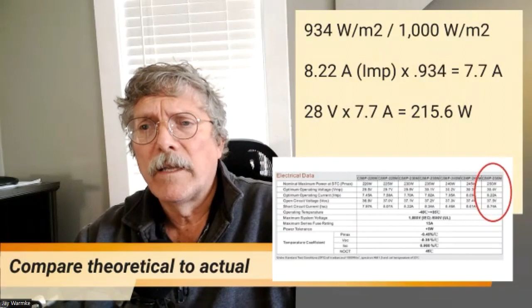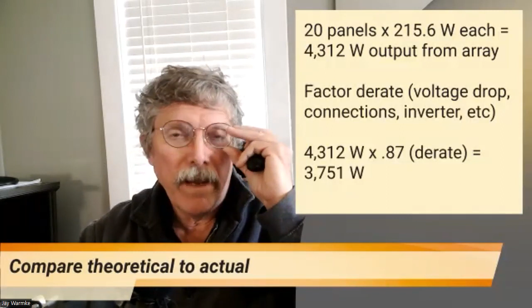So we take our 28 volts times our 7.7 amps, because watts equals amps times volts. And we find that this panel, which was rated for 250 watts, should, under the conditions we're experiencing at this moment, produce about 215.6 watts. So that is when it's working as designed, perfectly. All right, but there's more than one panel in this system. There are actually 20 panels in this array. We had an array of 20 panels, 250 watts per panel. That's our 5 kW system. So we take 20 times 215.6, and we find that the array is now outputting 4,312 watts.